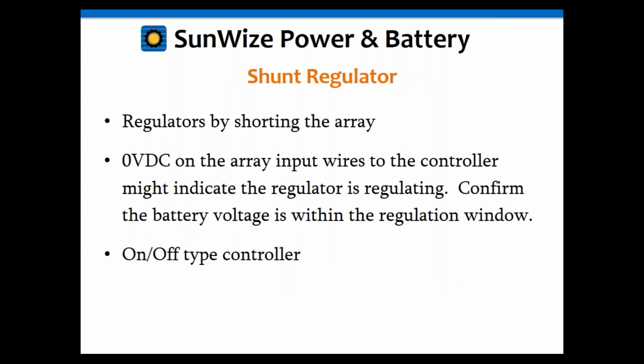Okay, a shunt regulator works by shorting the array. That's how it regulates. So if you're reading 0 volts on the array input wires, there's a good chance that the regulator is regulating. And this goes back to the battery voltage again: confirm the battery voltage is within that regulation window. The shunt regulator is an on-off type, which means the battery will go up to what they call the disconnect voltage, and it will disconnect the array, and when that voltage drops slowly, it'll reconnect it again. Typically, for a 12-volt system, the disconnect is somewhere around 14.1 volts, and the reconnect might be like 13.8 or 13.7, something like that. So if your battery voltage is within that window and you're seeing that your array voltage is at 0 volts, then there's a good chance it's regulating. So that's how you would tell if that charge controller is working correctly or not.